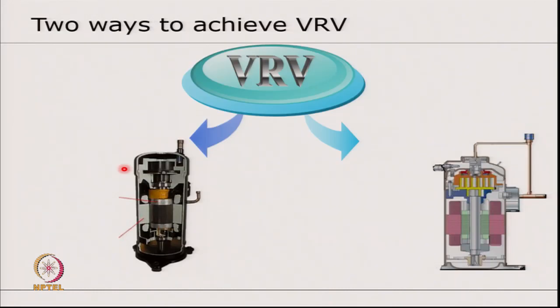And then the compressor speed variation, or the refrigerant flow variation, can be done in 2 ways. One is using a true variable speed compressor, which would offer much higher part load efficiencies, or using something like this, which is equivalent to bypassing hot gas. In effect, what we are doing is unloading the compressor by moving one of the scrolls up so that there is no compression happening.